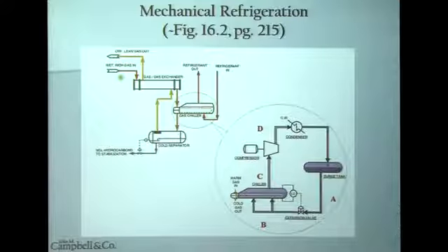This is our rich gas that comes into the system. It's hydrocarbon wet and water wet. It goes through a gas-to-gas exchanger where the gas coming out is now a two, or actually three-phase mix.